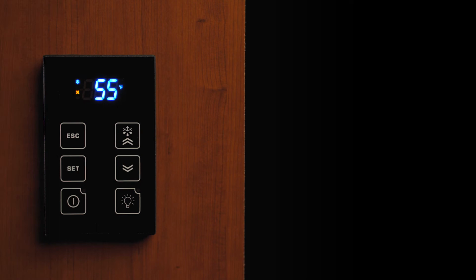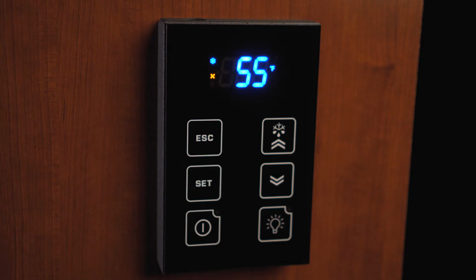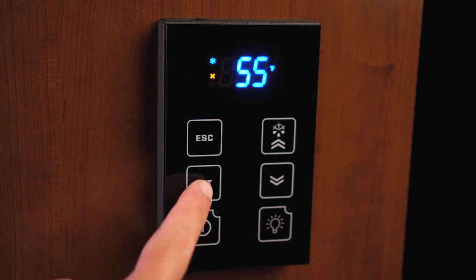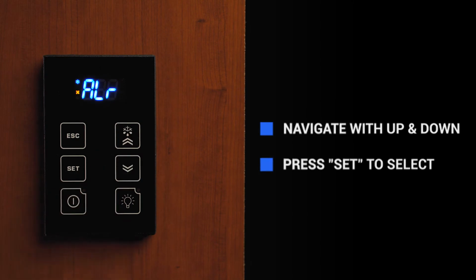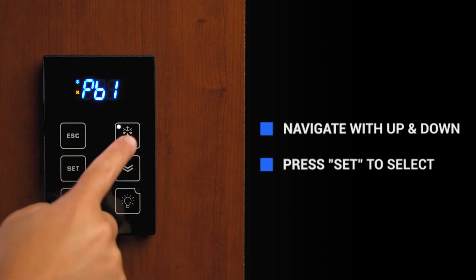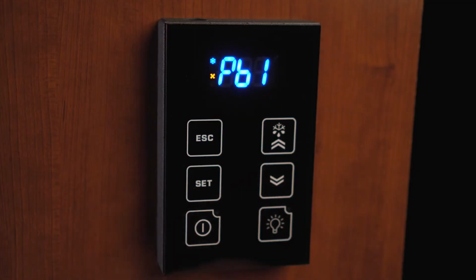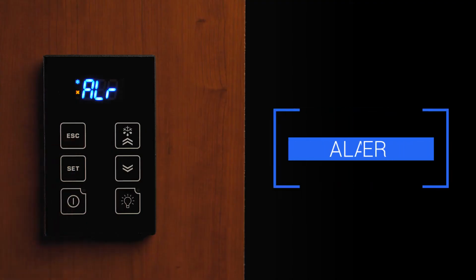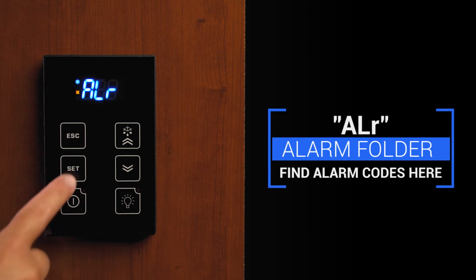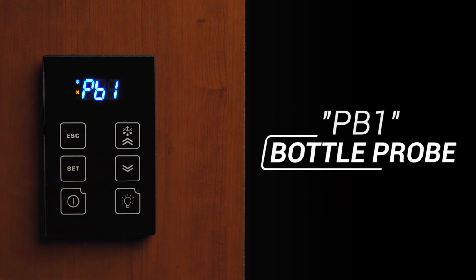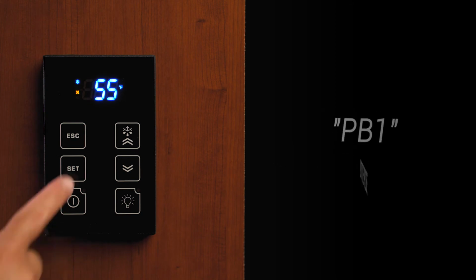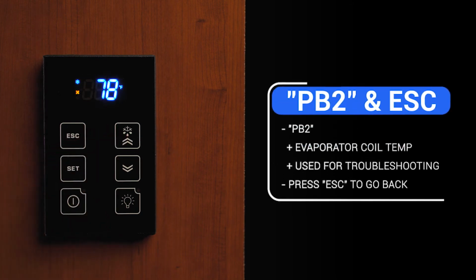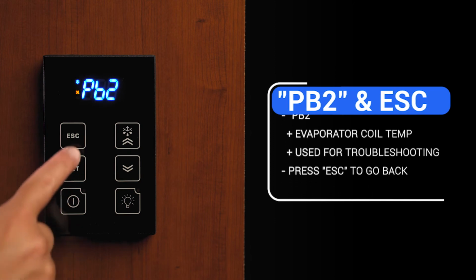To navigate through the different folders on the main control display, you will need to unlock the keypad, then press the Set button. Use the up and down arrows to scroll through the ALR, PB1, or PB2 folders. At each folder, you will need to press and release the Set button to see the parameters of that folder. The ALR is the alarm folder. If the alarm icon is displaying, you will find the code for the alarm in this folder. The PB1 is the bottle probe temperature, and the PB2 is the evaporator coil temperature, which we may use for troubleshooting purposes. Pressing the Escape button returns you to the previous menu.